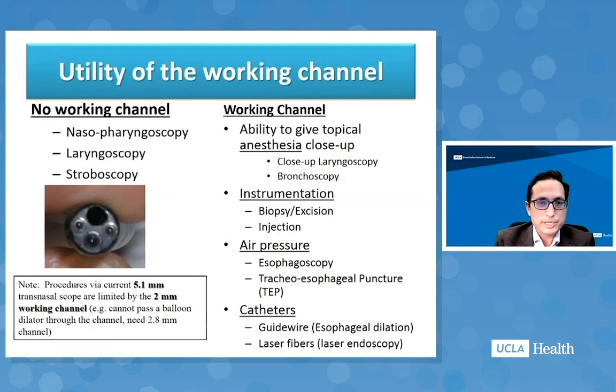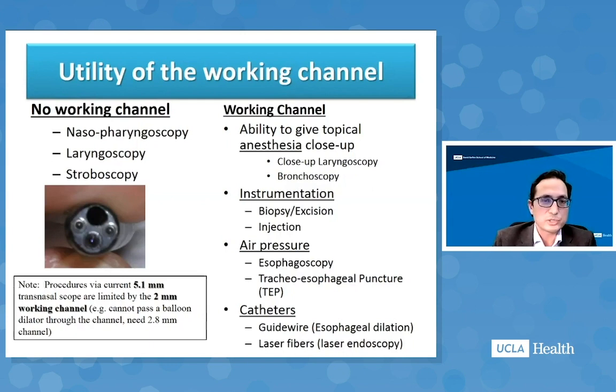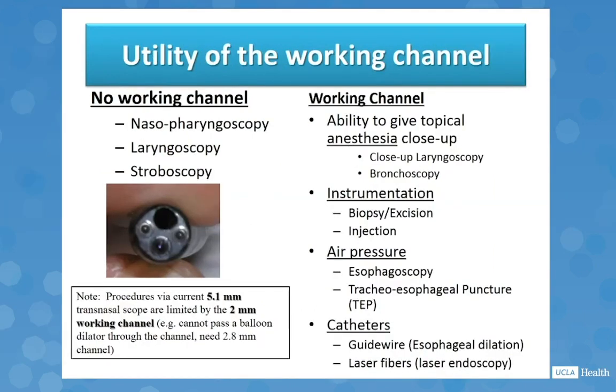One thing to remember is that currently the transnasal endoscopes are typically 5.1 millimeters or less with a working channel that's two millimeters in diameter, so you cannot pass instruments or balloons that require a channel of 2.8 millimeters.